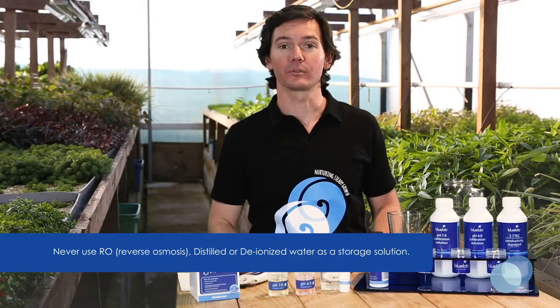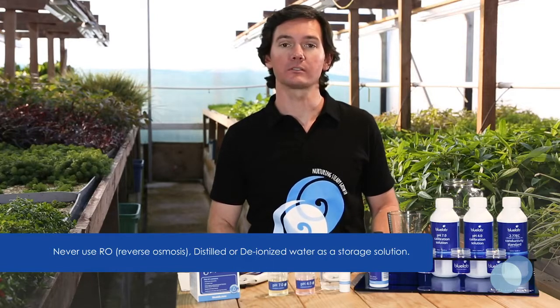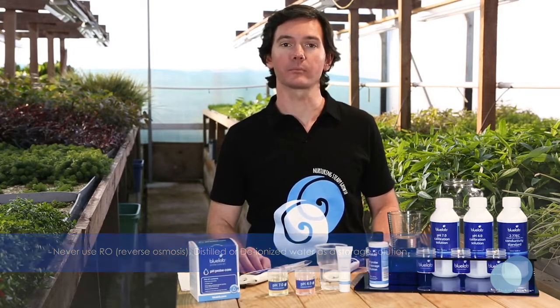Remember never to store your probes in reverse osmosis or RO, distilled or deionized water. These types of pure water can change the chemistry of the probe glass and cause damage to your probe.